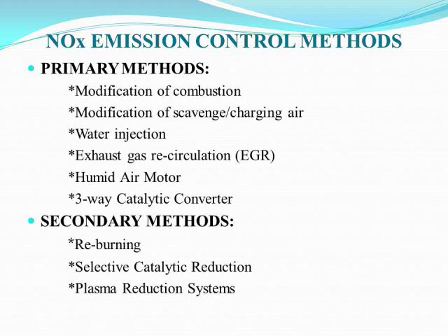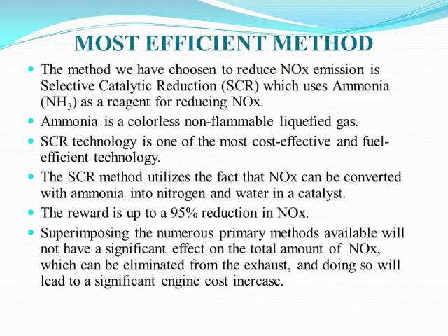What are the NOx emission control methods? Primary methods are: modification of combustion, modification of scavenged charging air, water injection, exhaust gas recirculation, humid air motor, and three-way catalytic converter. Secondary methods are: reburning, selective catalytic reduction, and plasma reduction systems.